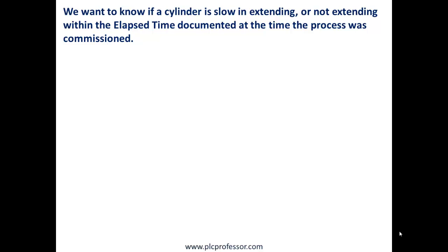And you're going to do this to monitor the time intervals between the command and the completion of cylinder motion. So from the time that you energize the output to extend or retract the cylinder until it's actually sensed by the end of stroke sensors that it's been completed. Now, most projects do not budget for these features, so they seldom get implemented unless the end user does so after the fact, and you know that seldom occurs because everybody's busy. So if you can add these diagnostics at little cost, your machine has an edge on the competition.